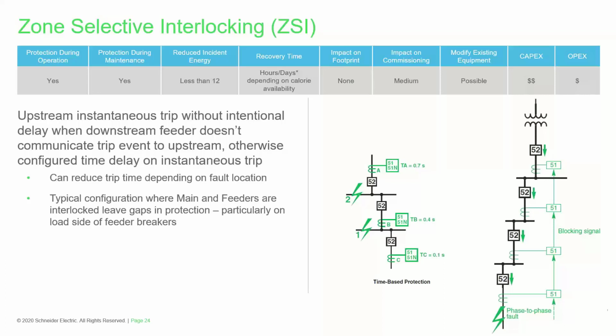So we give you some ideas up at the top. That's the row from the matrix in the guide. How much incident energy reduction are you getting? How much impact on commissioning is this going to have? This time we say it's medium, because if you want to fully test out the ZSI system, it's more involved than just secondary injection testing of a breaker in a standalone application. It adds a little bit to the cost. Then Jeff talked about those application notes. For example, a typical configuration may leave some holes in the protection. In a typical configuration where you have mains and feeders interlocked, you're really not getting ZSI protection on the load side of a feeder breaker. So that's something to consider as you look at this.